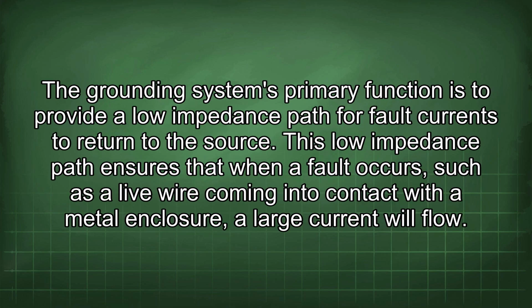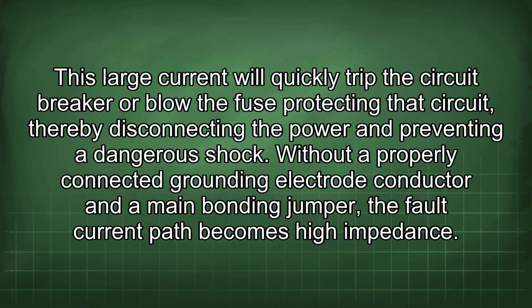The grounding system's primary function is to provide a low impedance path for fault currents to return to the source. This low impedance path ensures that when a fault occurs, such as a live wire coming into contact with a metal enclosure, a large current will flow. This large current will quickly trip the circuit breaker or blow the fuse protecting that circuit, thereby disconnecting the power and preventing a dangerous shock.